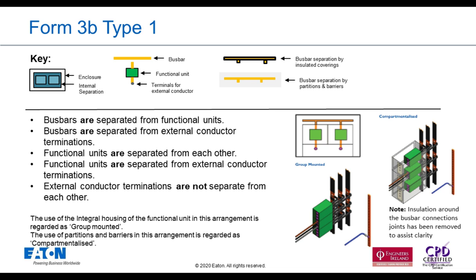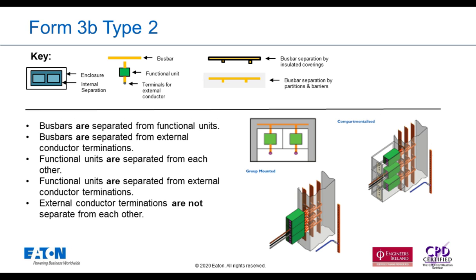Then we have Form 3B Type 1. Now, there's a couple of ways of doing this. You can either do it as group mounted or compartmentalized. Group mounted, obviously, we just spoke about. We're using the housing of the protected device as a means of isolation. And on compartmentalized, we're now using an enclosure to separate each functional device. And obviously being type 1, the main bus bar is separated from the external cable terminals using insulating material. And type 2, we're using a barrier or a partition to separate the main bus bar from the external terminals.